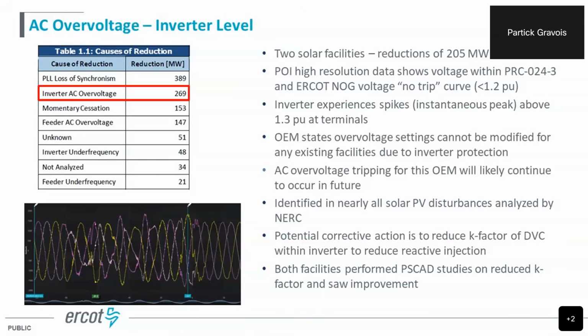So the only corrective action we were able to come up with is reducing the reactive injection. We were seeing that the reactive injection in response to the low voltage due to the fault was sometimes coming in a little late, a little bit too much, and it was causing this high voltage at the inverter terminals and causing these plants to trip themselves off. So this is an issue that was identified on several events. We've been covering it pretty well over these events as well. We did have these facilities start doing some PSCAD modeling to see what would happen if they reduce this K factor, and they did see improvement. Unfortunately, none of this got implemented before the 2022 event.